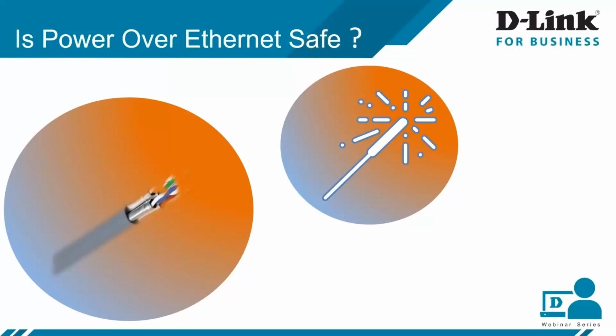Now there was a question: is power over Ethernet safe? A small brief on power over Ethernet. PoE has been around for several years, starting with type 1, introduced in 2003, which delivered up to 15.4 watt with 13 watt available to the device. Followed by PoE Plus technology, type 2, which delivers 30 watt with 25.5 watt available. At this level of DC power, no one really questioned whether PoE was safe or not. But once 4-pair type 3 and type 4 PoE were introduced in 2018 at 60 watt and 90 watt respectively, the National Electric Code was revised to address this 60 watt remote powering circuit. Then many started wondering whether PoE is safe or not. So let's have a look at this.